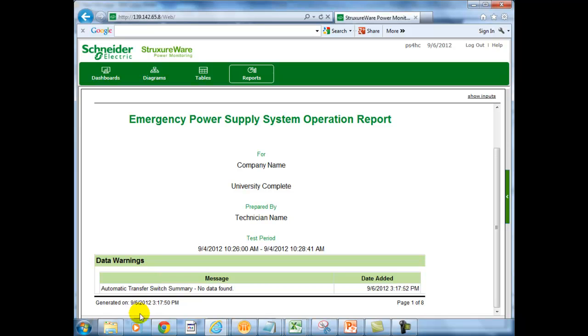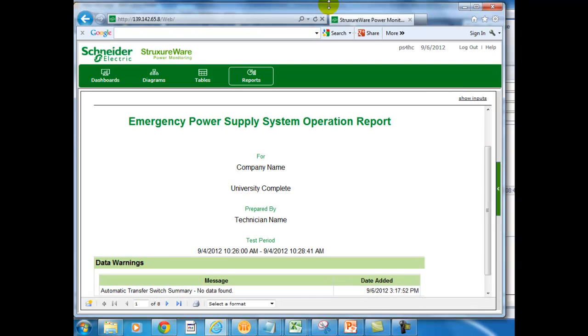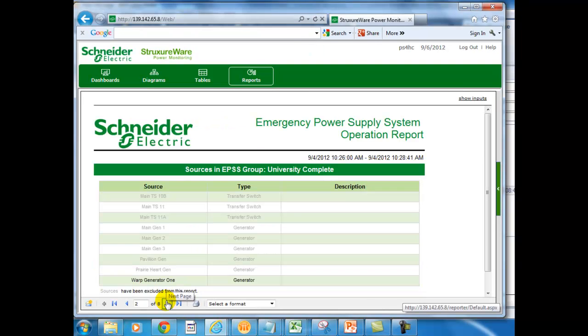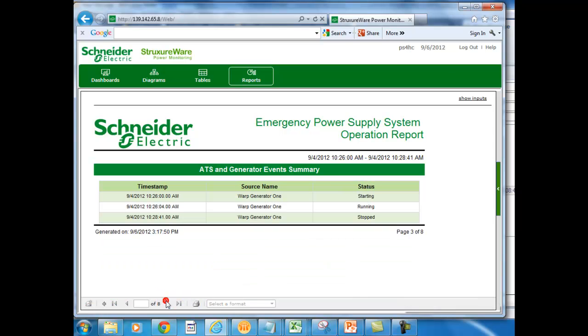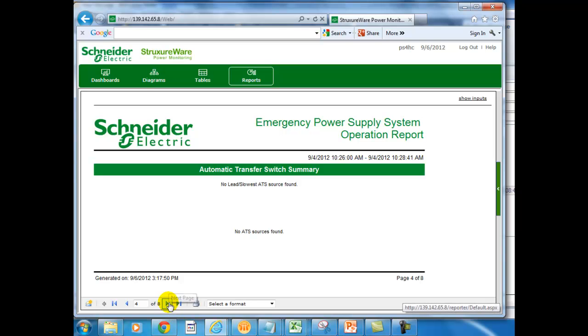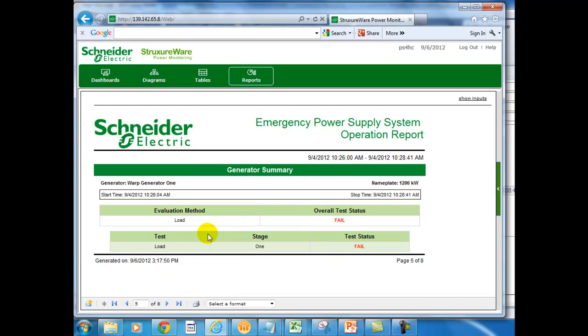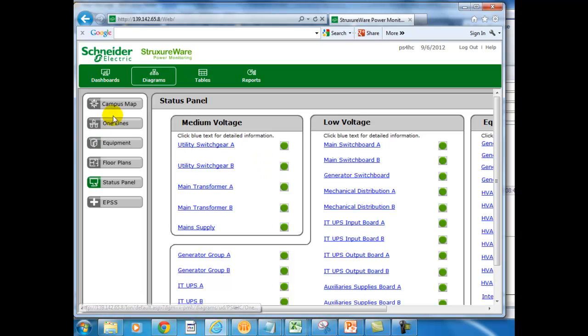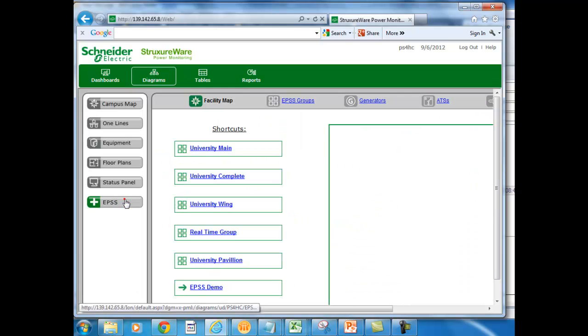Okay, here we go. So there's a sequence of operation as to what operated first, next with times, and here's the overall test status, which is a fail, probably because we didn't run the load bank, or we didn't run enough load that the test configuration specified. So that's a typical EPSS report. Let's do one more thing, which is simulate an actual EPSS test.